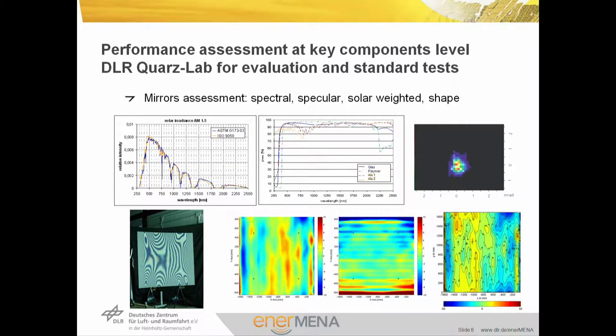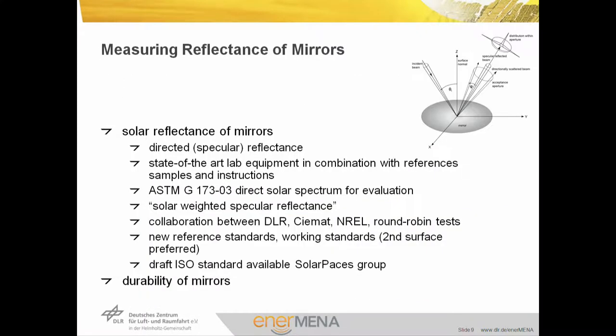Let's start on the mirrors as one of the key components. We assess the mirror quality in terms of reflectance: spectral reflectance measured in a spectrophotometer, specular reflectance measured with a reflectometer, and evaluate the solar-weighted properties. Measuring the reflectance of mirrors means measuring the direct specular reflectance relevant for the solar spectral range. The reflectance is measured with state-of-the-art lab equipment — spectrophotometers — in combination with references and appropriate instructions. The weighting is done with the solar spectrum from ASTM G173 for direct solar light, giving us the solar-weighted hemispherical and solar-weighted specular reflectance values. Such definitions have come out of collaborations between large test centers — DLR, CIEMAT, NREL — and in round-robin tests, and are reaching standard levels.